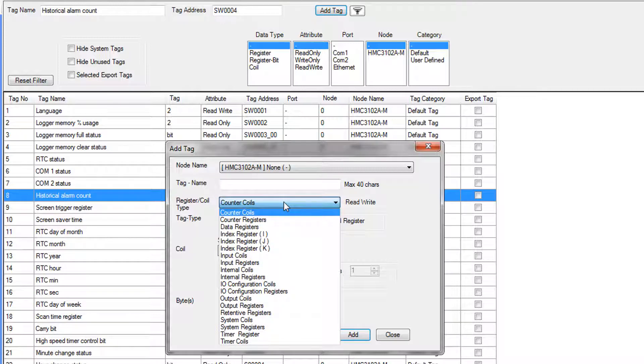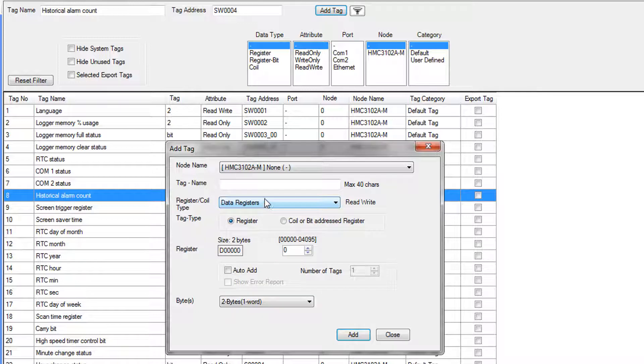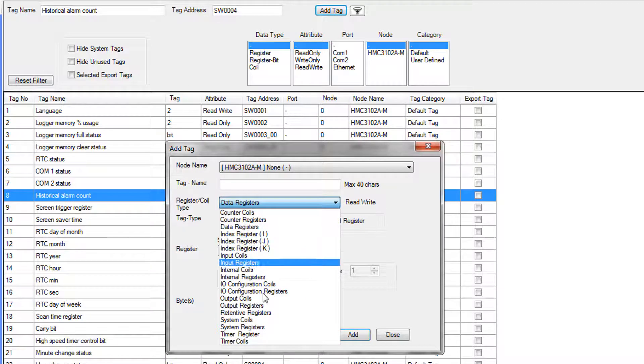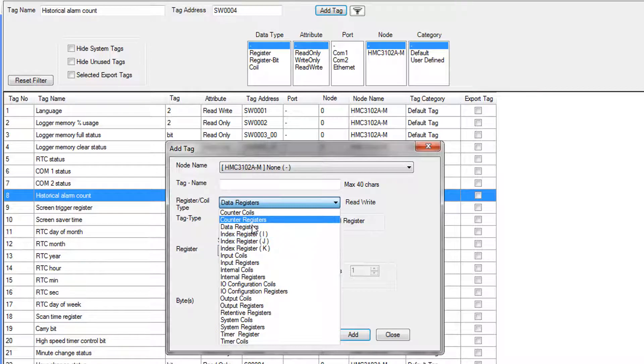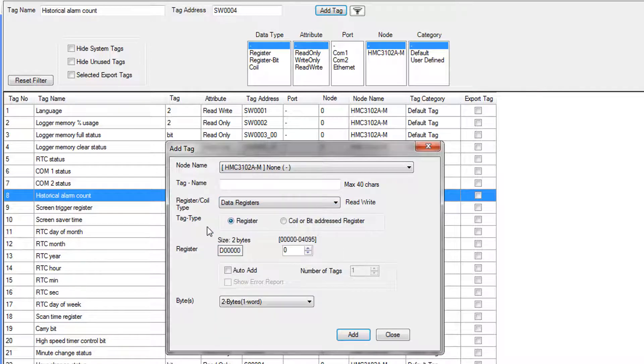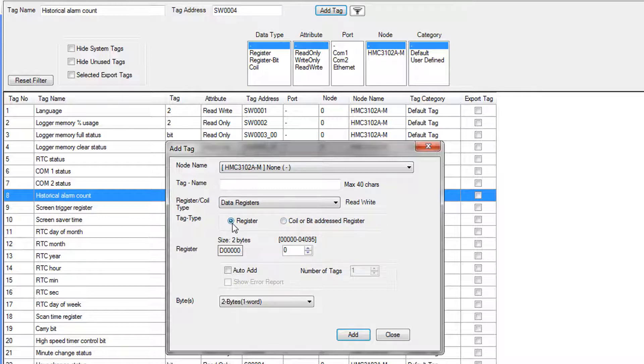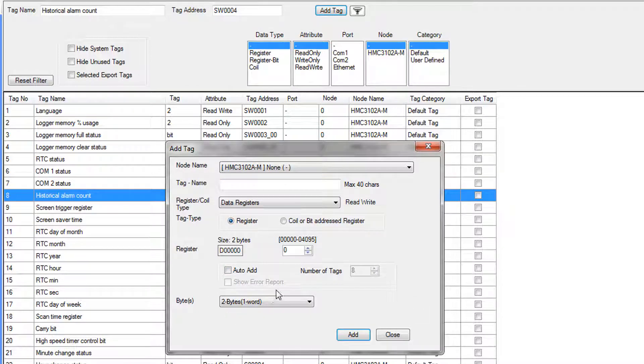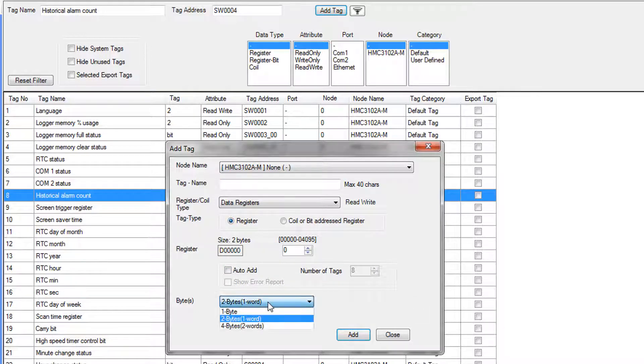Here's where you enter a name for your tag. You determine where in memory it's going to be stored. We are going to be using some data registers. This is a good listing of all the different types of memory that exist within the HMC. At first, we're going to create some register tags. We will create some bits or coil addressed tags later. You can create multiple tags at once if you want to. If you were going to auto-add and create 20 tags with basically the same name and just a number appended after that, you could.